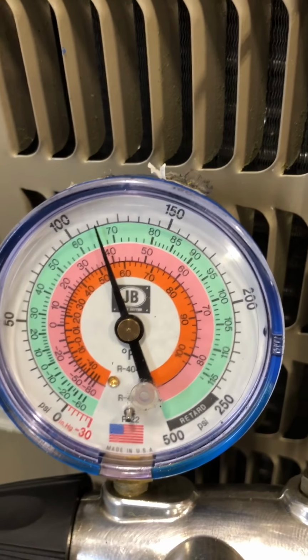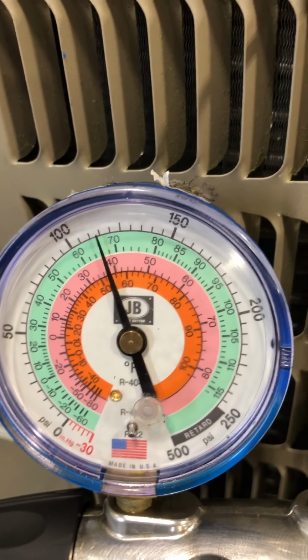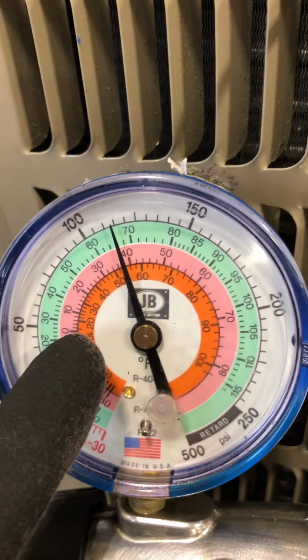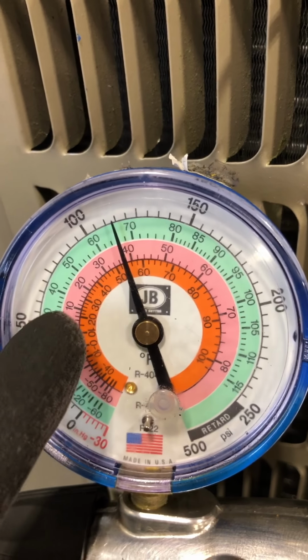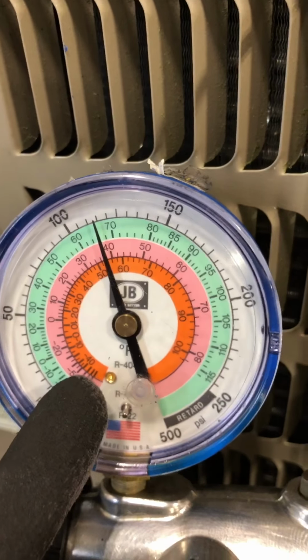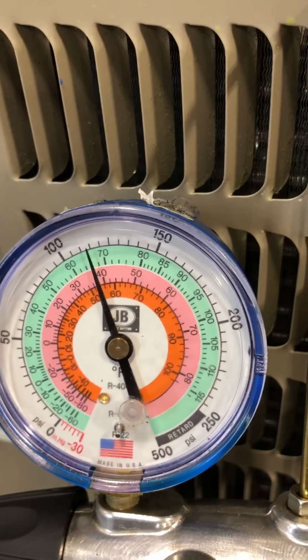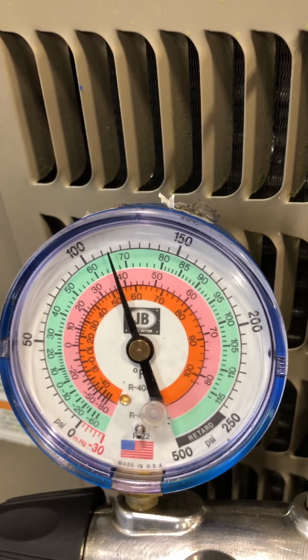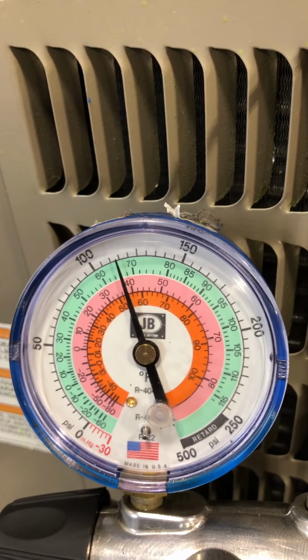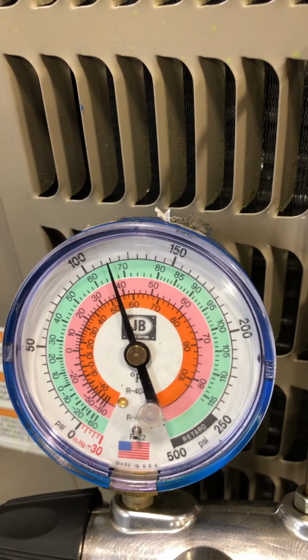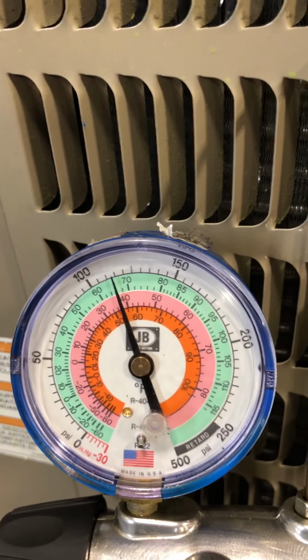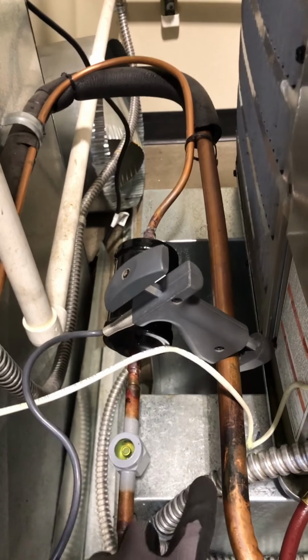Superheat: our boiling temperature, our saturation temperature in our evaporator. We're dealing with R410A, so we're looking at the pink stripe. If we were dealing with R22, we'd be looking at the green one, and so on. But we're dealing with 410 today. So we're saturating that low pressure liquid vapor mix at 38 degrees, and we're boiling it into vapor at 38. I've got my temperature probe on my vapor line.